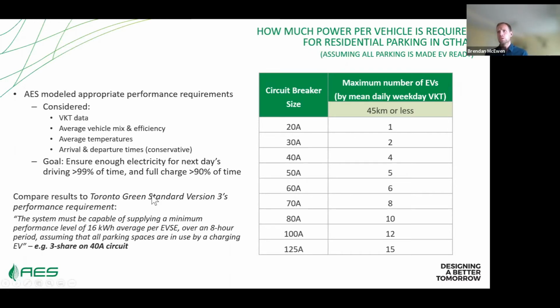I'll note that right now, the Toronto Green Standard version 3 allows essentially for 3 sharing on a 40 amp circuit. It says the minimum performance level is 16 kilowatt hours average per EV over an 8-hour period, assuming all parking spaces are used by a charging EV. That equates to 3 sharing on 40 amp or 6 sharing on 80 amp.